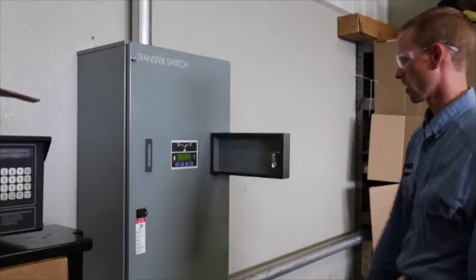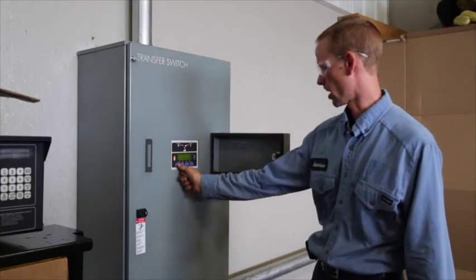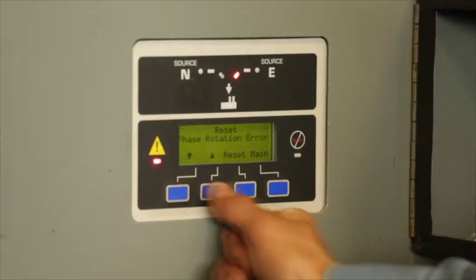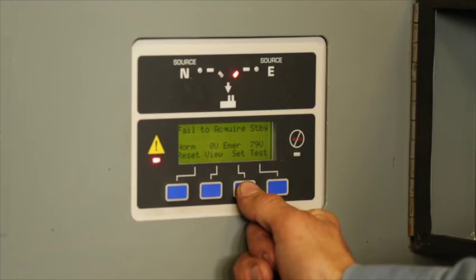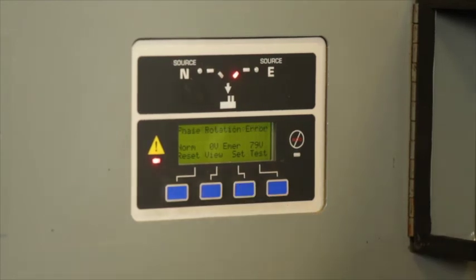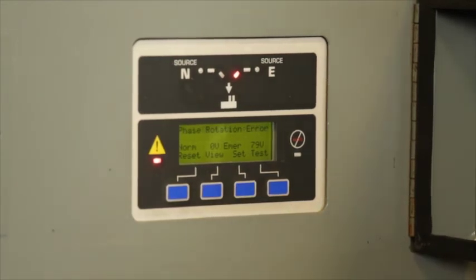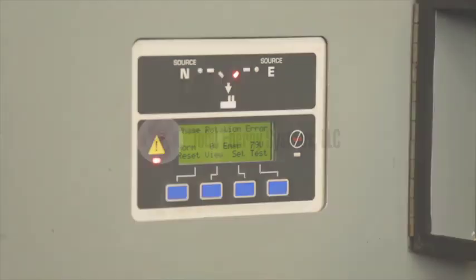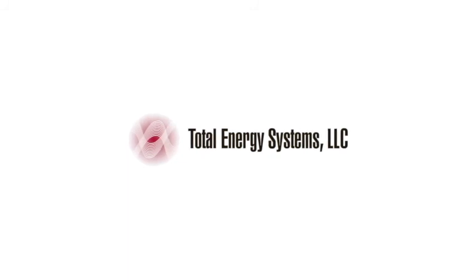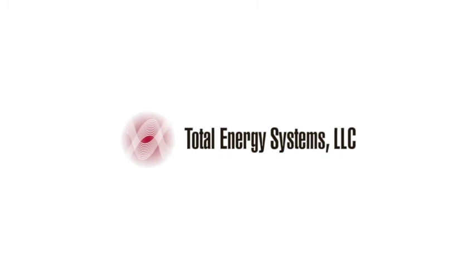If a fault such as this occurs, first you can press the Reset button and then press the Set button. If, as in this case, the fault comes right back, you should write down the fault indicated and call your ATS service provider. If you are unable to correct the issue after checking for any of the faults covered in this video, you should call your generator service provider and provide the model and serial number.